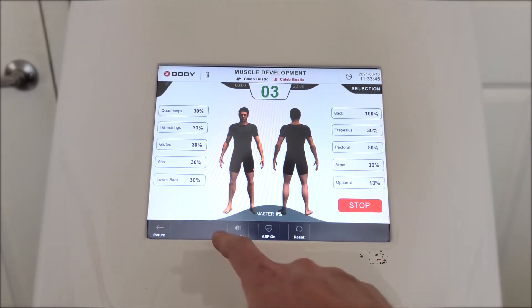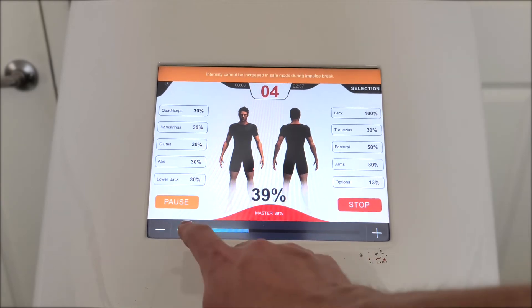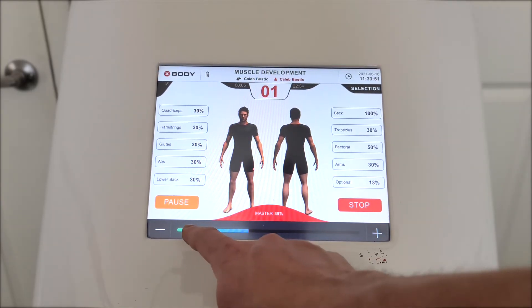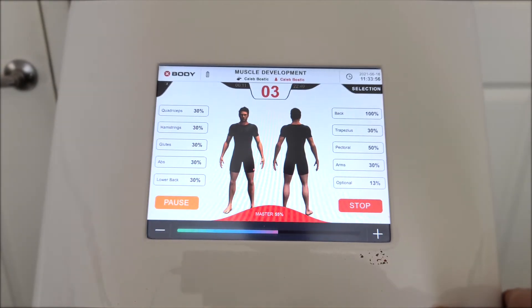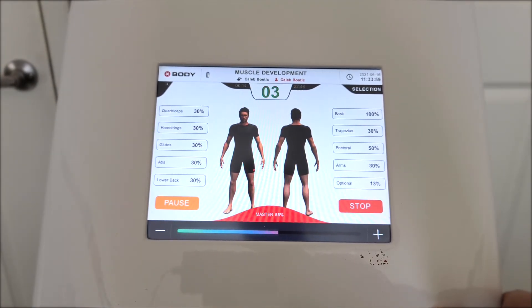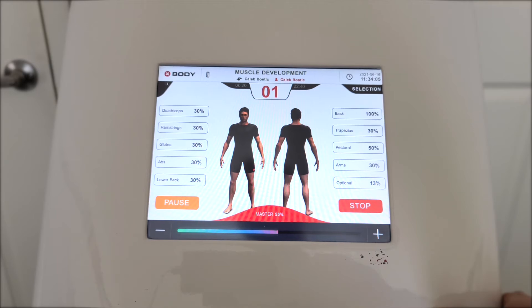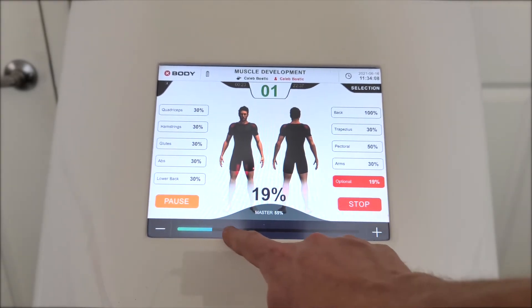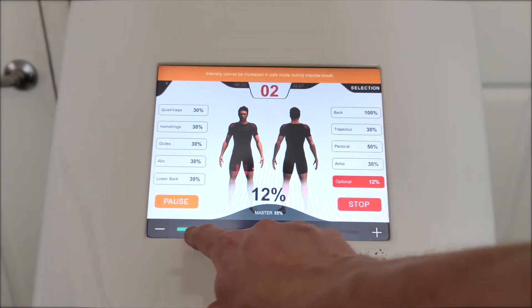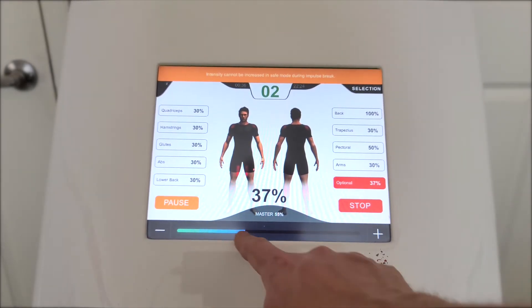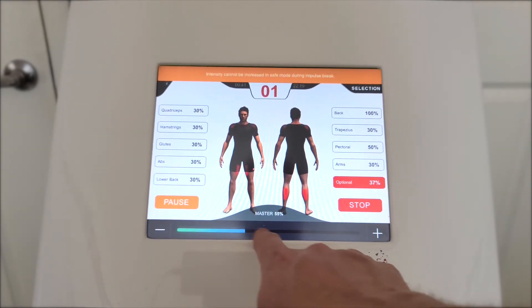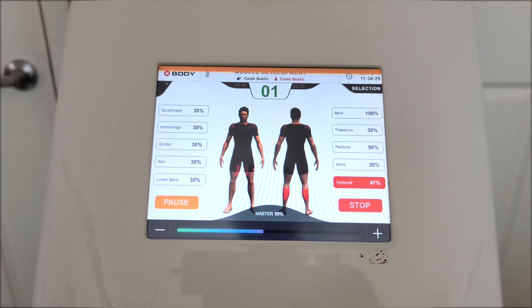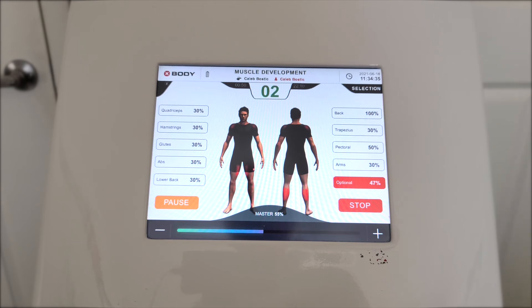If we go ahead and start a workout, you can see we've got a master control that brings all of the different stimulations up at once. At the top there's a countdown in green and red. In the red, the client is resting with no stimulation at all. During the green, stimulation is provided to all of the electrodes at the set intensity. If you try to change the intensity during the rest period, you'll get a message at the top — that's to prevent accidentally turning something up during rest so the stimulation doesn't come back on much higher than the client is ready for. It's a little safety measure built in.